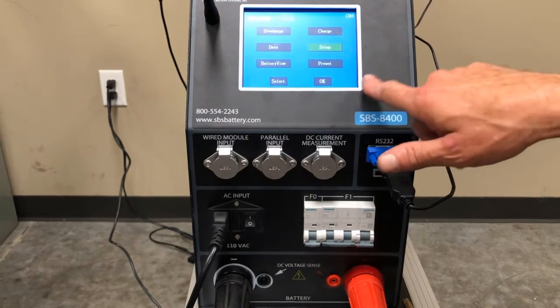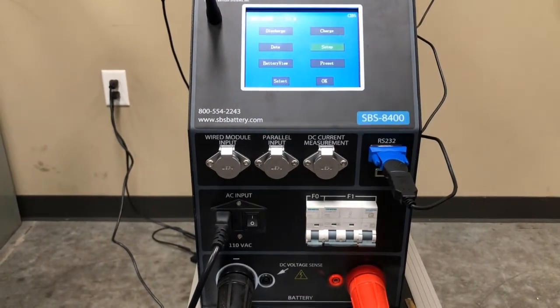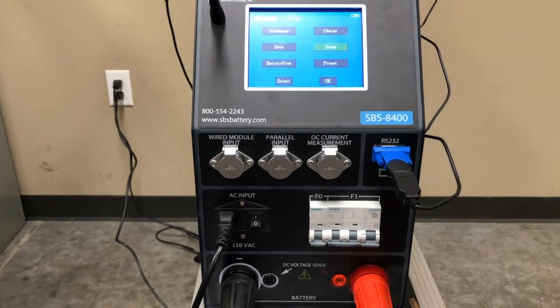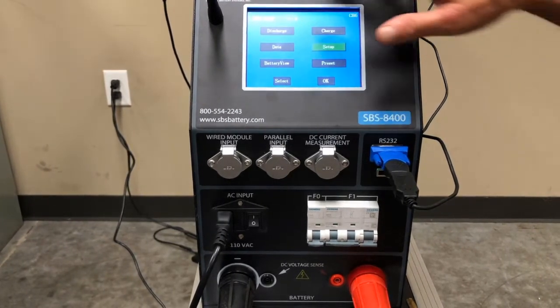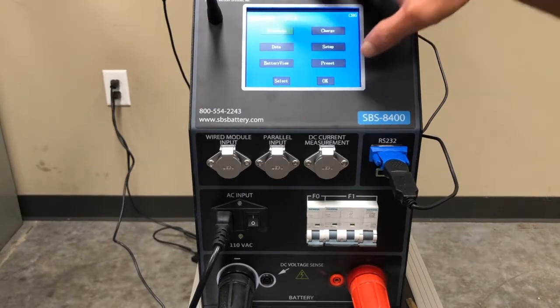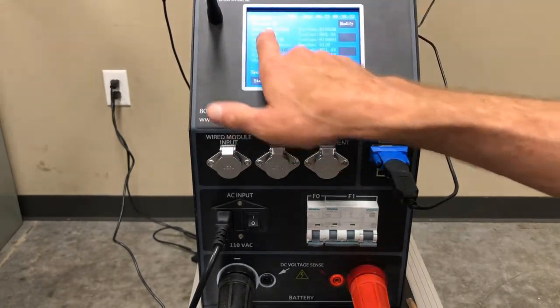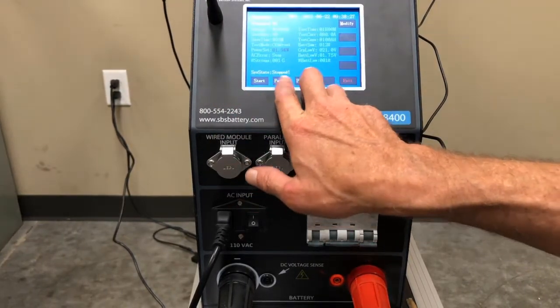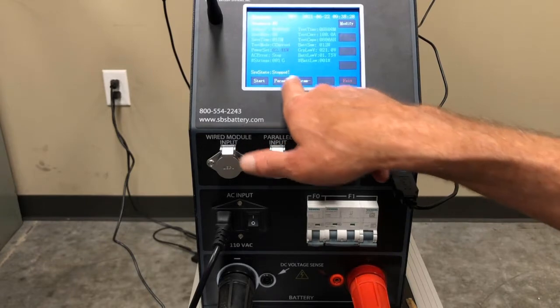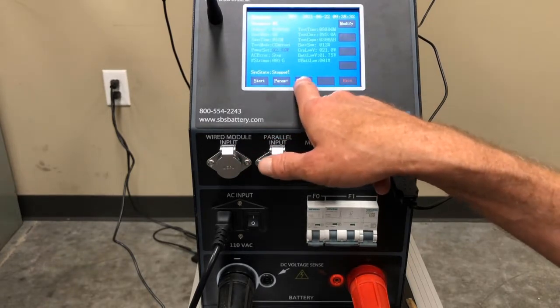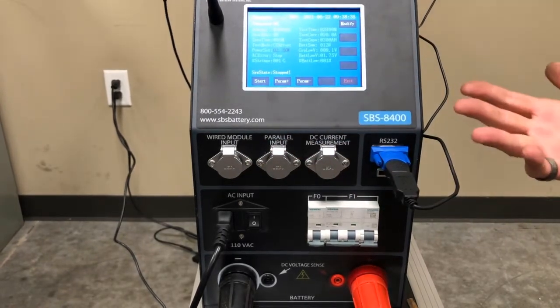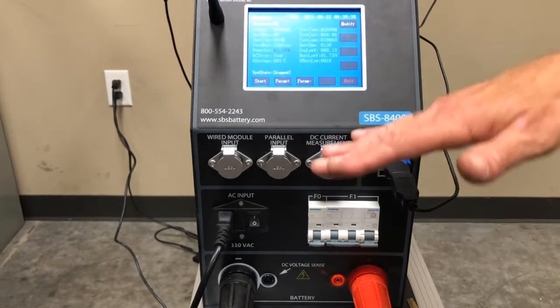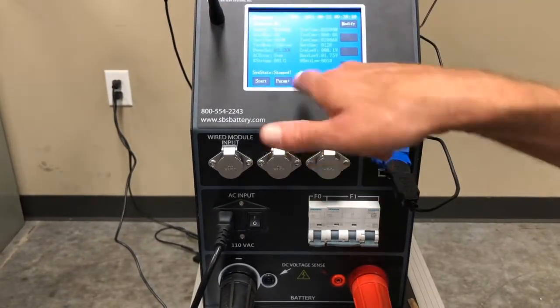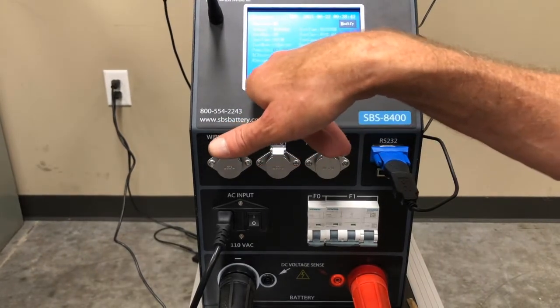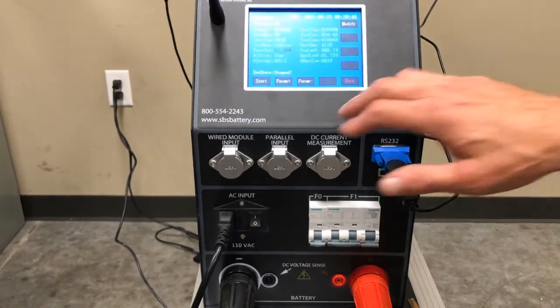So we'll exit out of that setup screen. That automatically saves any changes that you make in the setup screen. Automatically saves when you exit out of the screen. We're going to go into discharge. And now you can see we're in preset parameter number 1. If you use the parameter plus and minus, you can have up to 30 different presets programmed into the 8400 unit. So once you've got a preset test set up, you just have to select that preset and press start, and it's going to run that test.